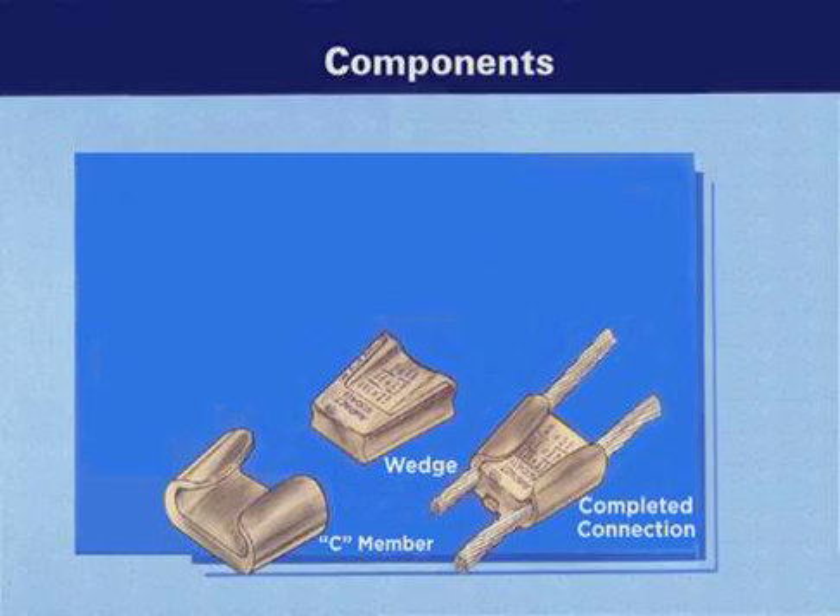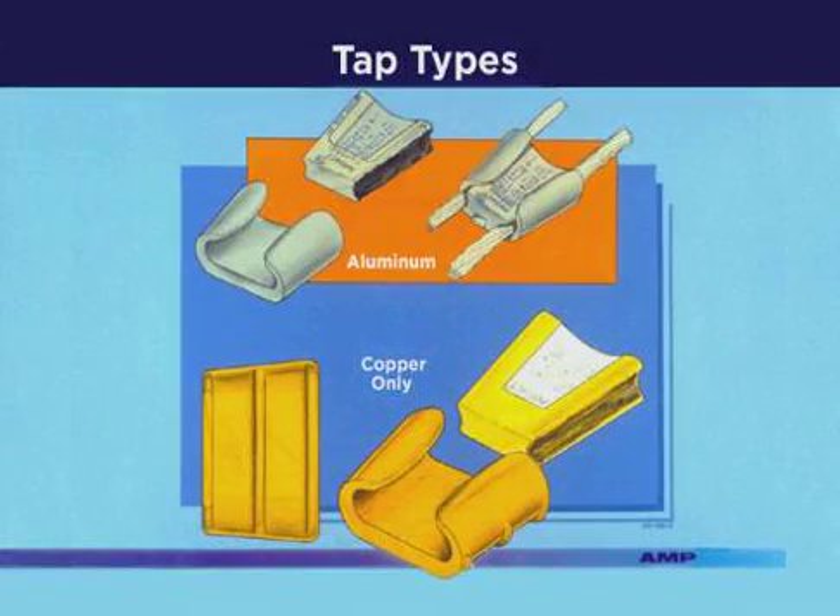The TAP consists of a wedge which is forced by the tool into the C member. Both the wedge and C members are supplied with a synthetic oxide inhibitor compound. AMPACT has available two types of TAPs: aluminum and copper.